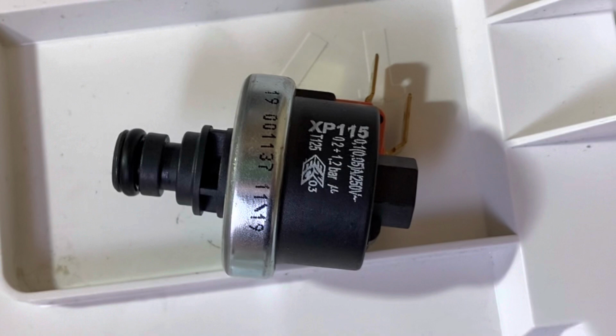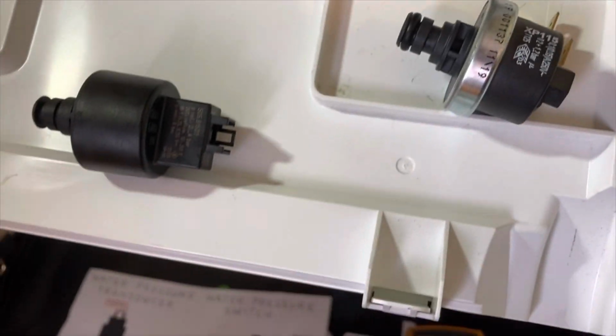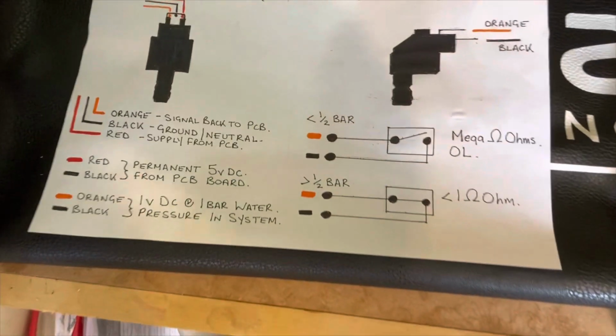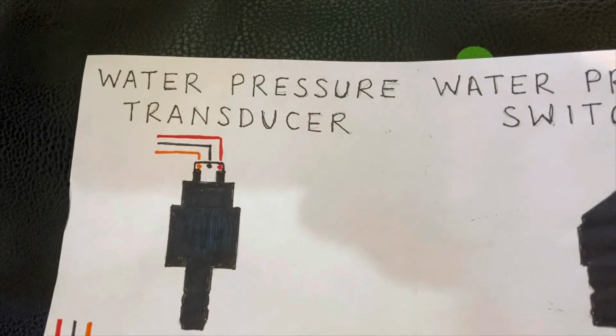But in our principle, it's just an open and close switch, which makes it really simple. It works on the premise of half a bar of pressure within the system will move the diaphragm and push the push rod onto the micro switch, creating the circuit, and below half a bar it will break the circuit, so it will be open. An open circuit will read either open loop, open line, whatever you want to call it, or mega ohms, and a closed circuit will read 1 ohm. So I've done a bit of a diagram, as you come to expect now.